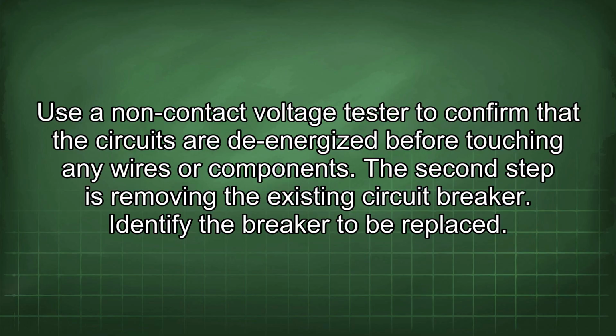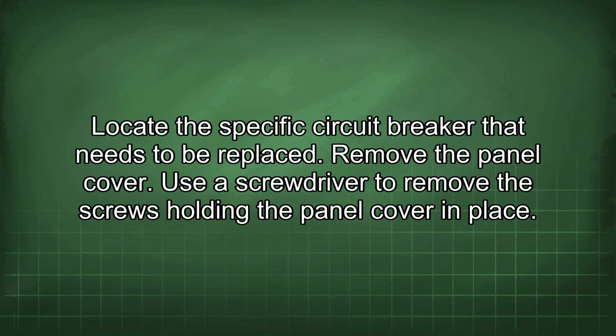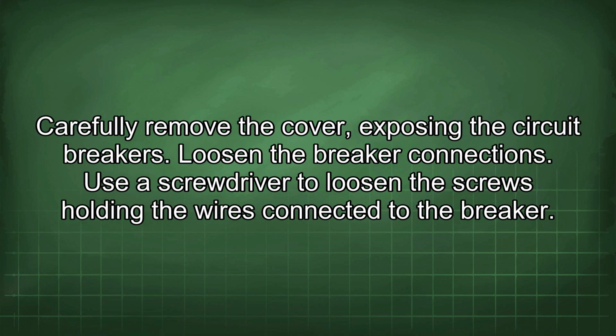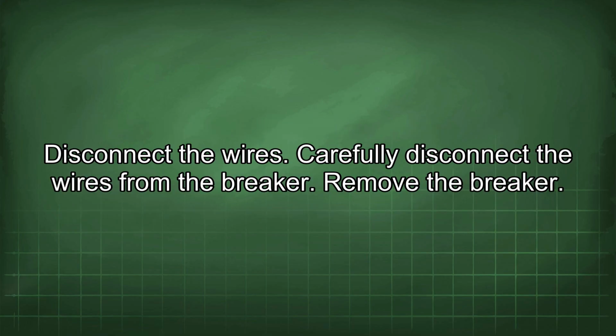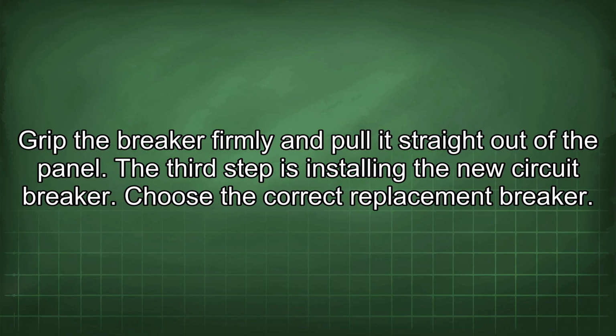The second step is removing the existing circuit breaker. Identify the breaker to be replaced. Locate the specific circuit breaker that needs to be replaced. Remove the panel cover. Use a screwdriver to remove the screws holding the panel cover in place. Carefully remove the cover, exposing the circuit breakers. Loosen the breaker connections. Use a screwdriver to loosen the screws holding the wires connected to the breaker. Disconnect the wires. Carefully disconnect the wires from the breaker. Remove the breaker. Grip the breaker firmly and pull it straight out of the panel.